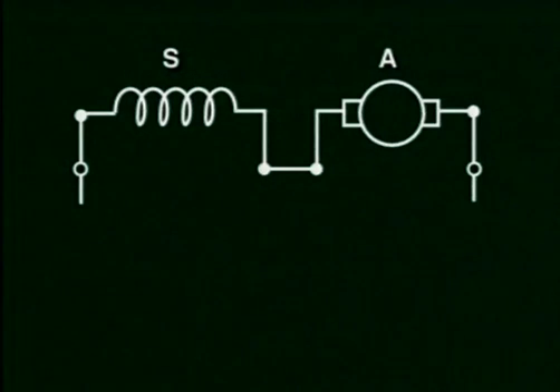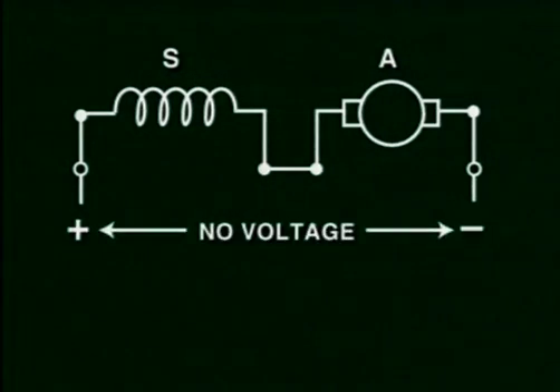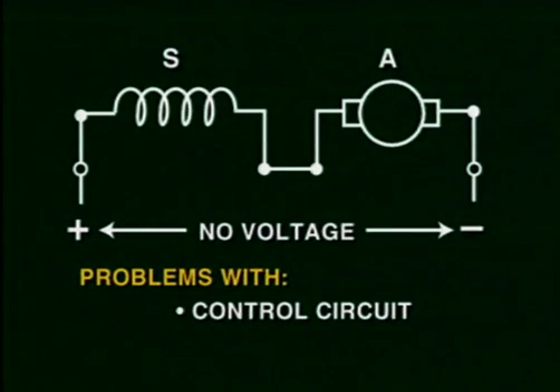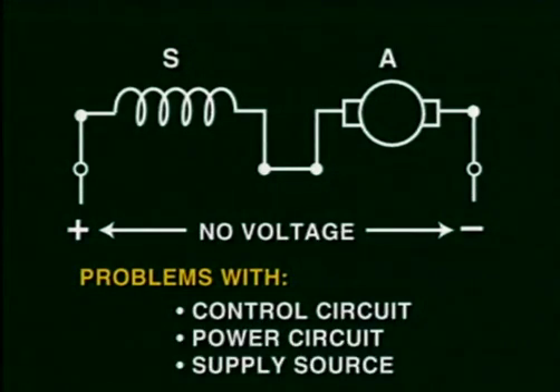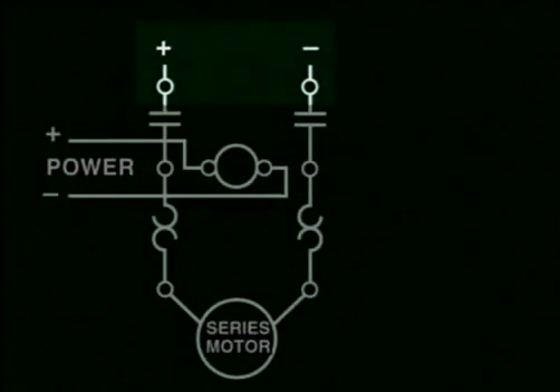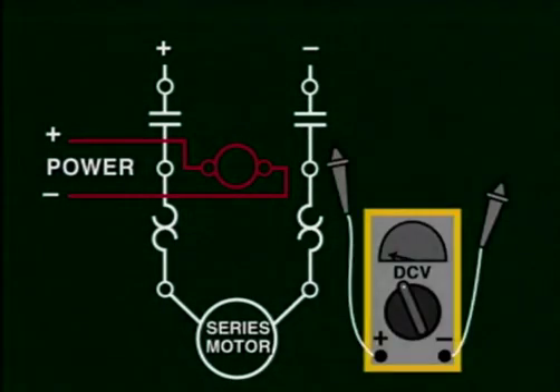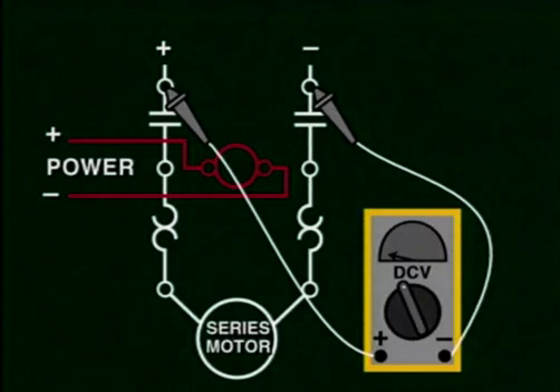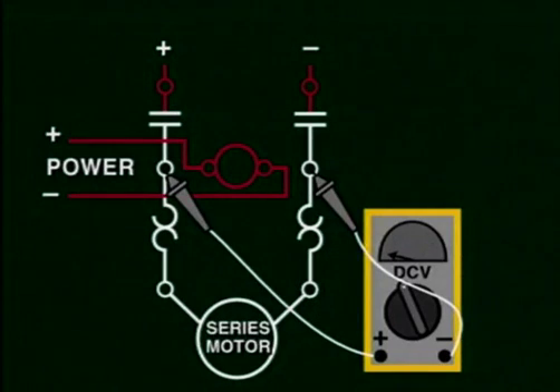The second cause for the motor not to start, due to no voltage at its terminal, will be due to a line voltage problem in the control circuit, in the power circuit, or in the supply source. In this module, we're going to cover troubleshooting of the power circuit and of the motor itself. If there is no voltage at the terminals and there is power to the starter coil, then check the voltage with a voltmeter set to a DC reading at a terminal point before the power contacts. If there is no power, then you need to check the main DC power supply. If you have power in the supply side of the contacts, then check the load side. If there is no power, then there is a problem with the starter coil and contacts.